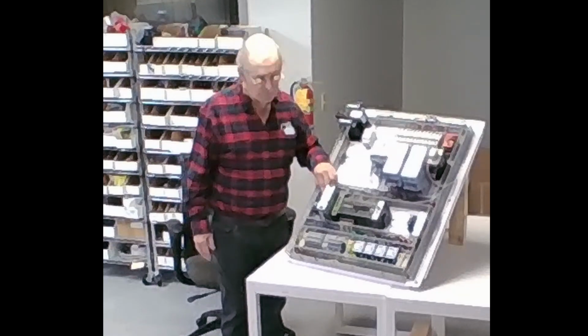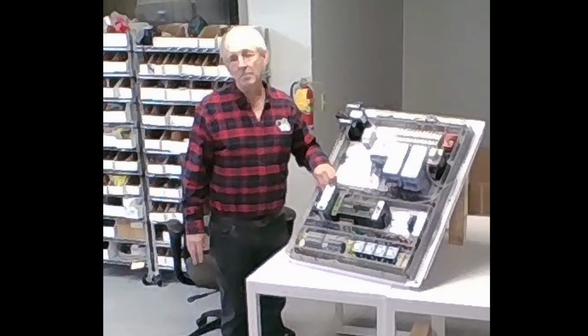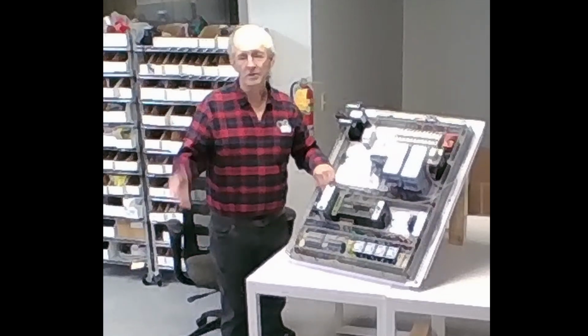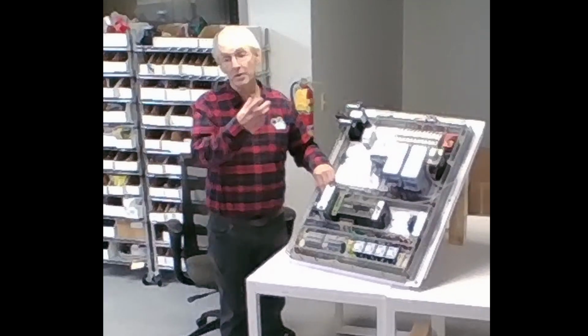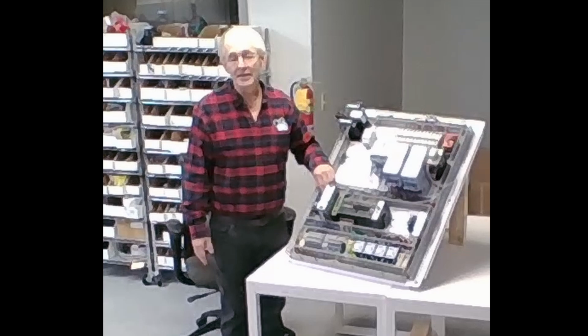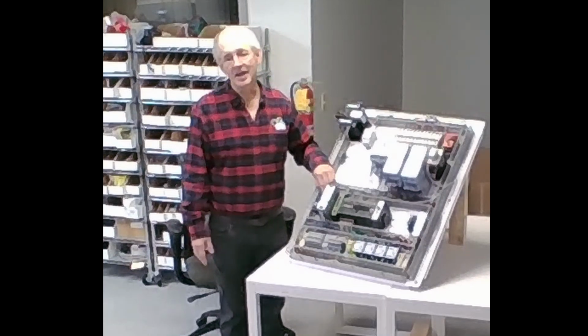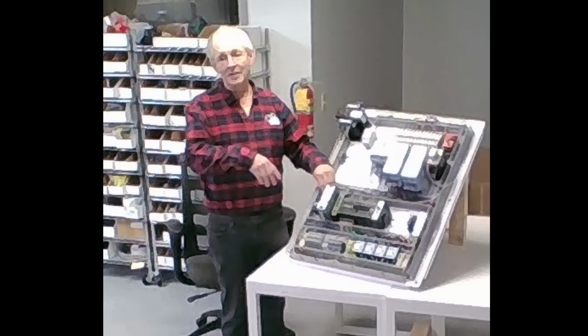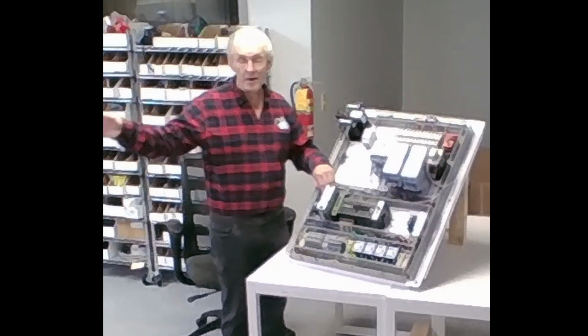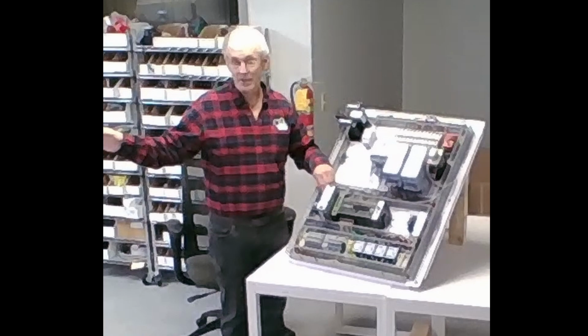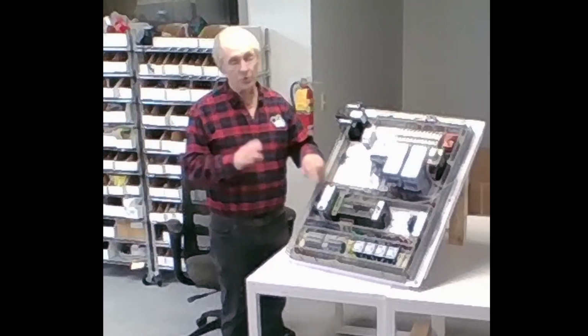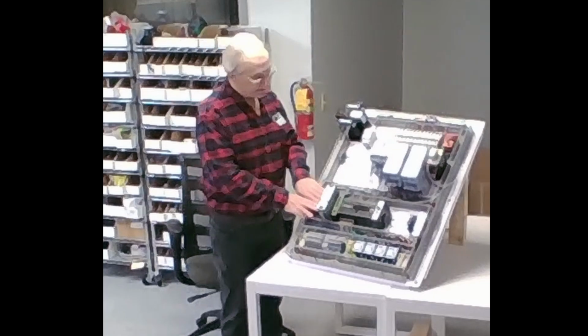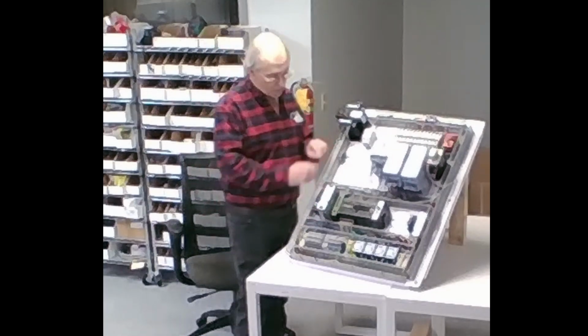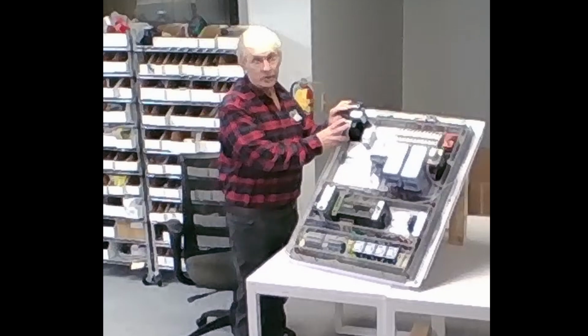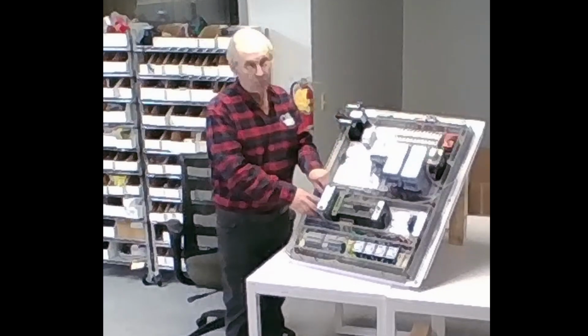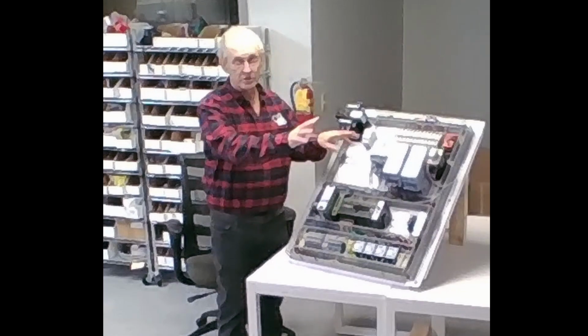Just like in your house panel, if you add up all the circuit breakers, you might have 300 amps worth of breakers, but the main breaker says 100. That's because the main breaker protects the cable coming into your house, and the other breakers protect the wires within the house. We're doing the exact same thing here. We have essentially a small power panel. We have one breaker, the main, that protects the transformer and the wires from that, and then 4 more that go out to the sub-circuits.